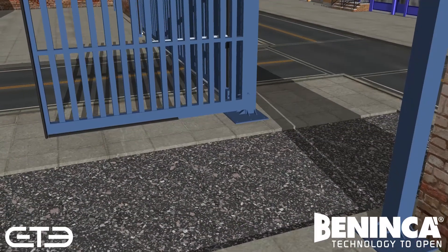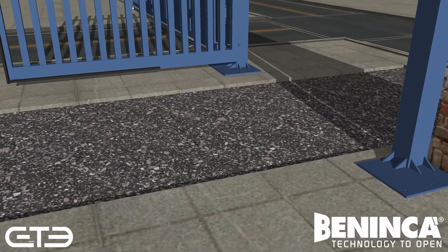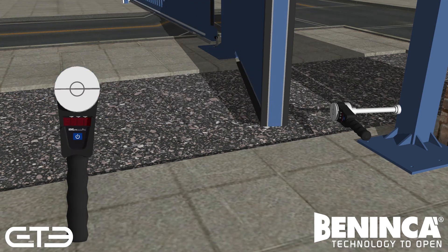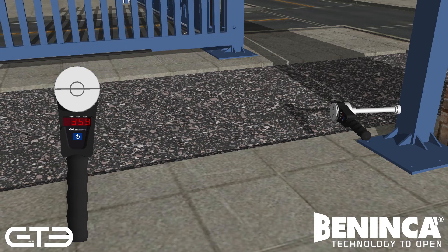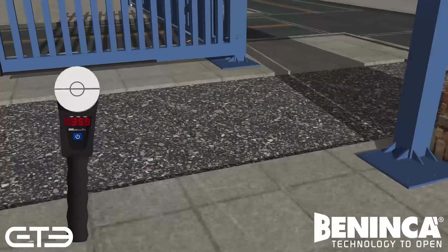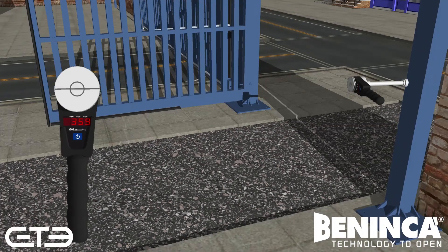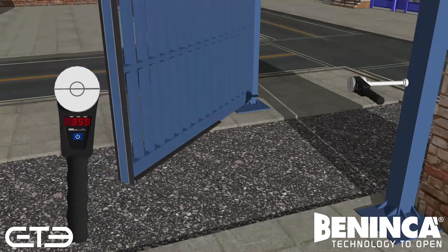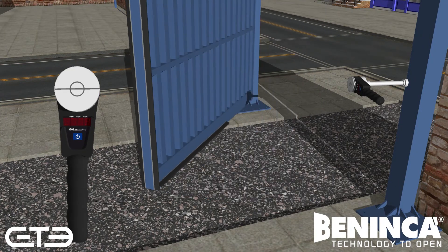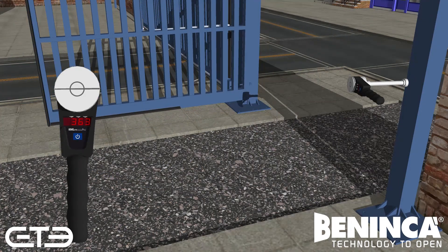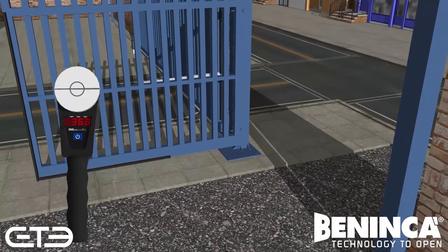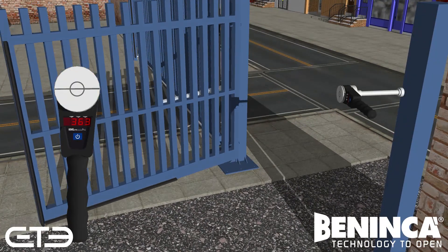For the next test, attach the first extender to the instrument. Place the extender against the stop post for your 10th reading at 50mm up and 300mm across. Initiate and test three times to gather your results for the average. Repeat for halfway up, 300mm across, and then 300mm down, 300mm across.